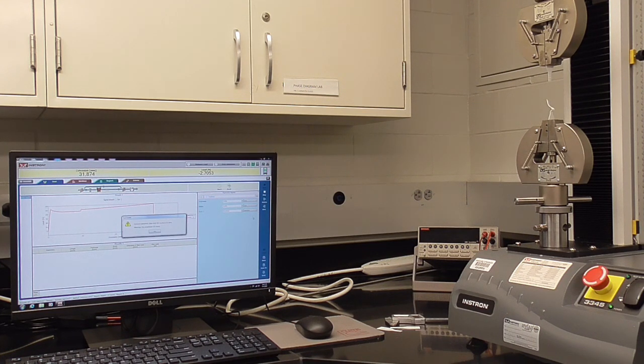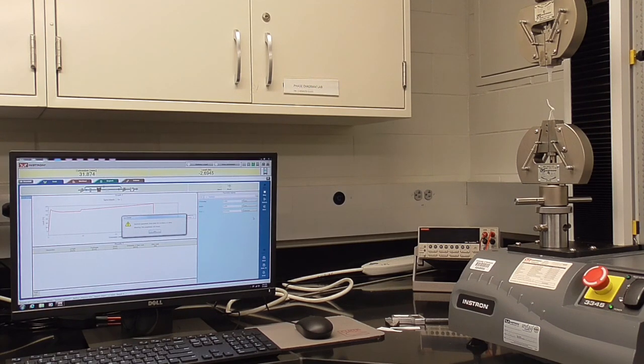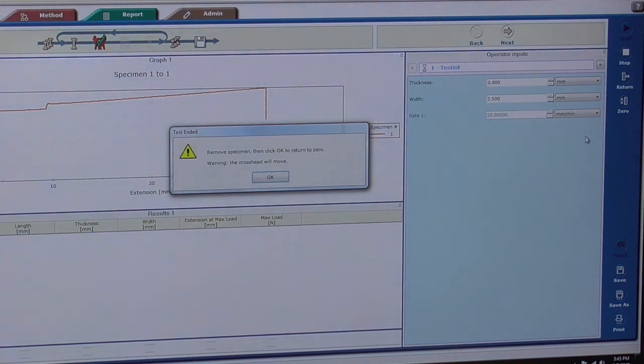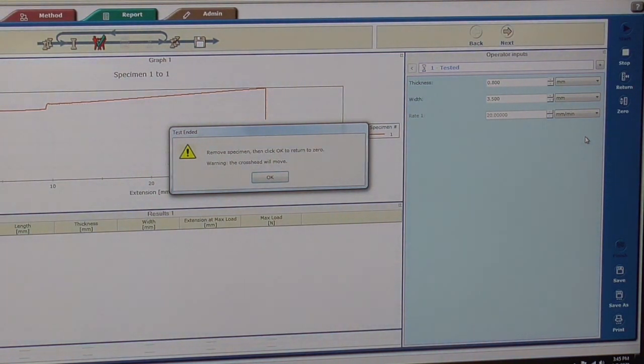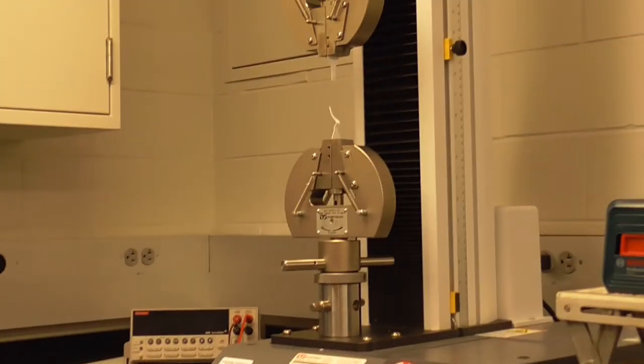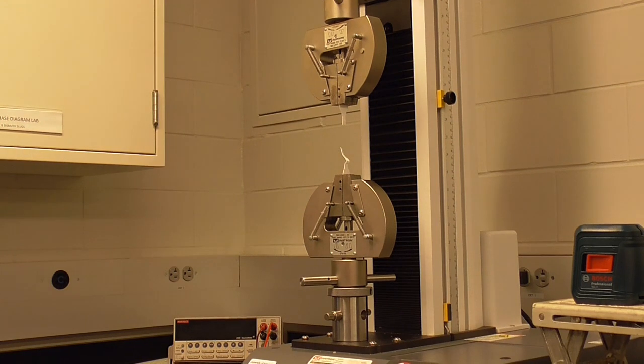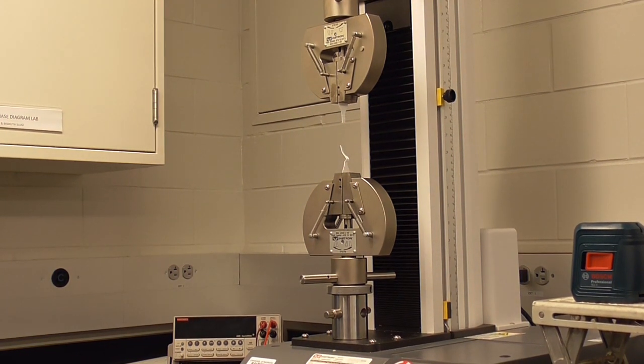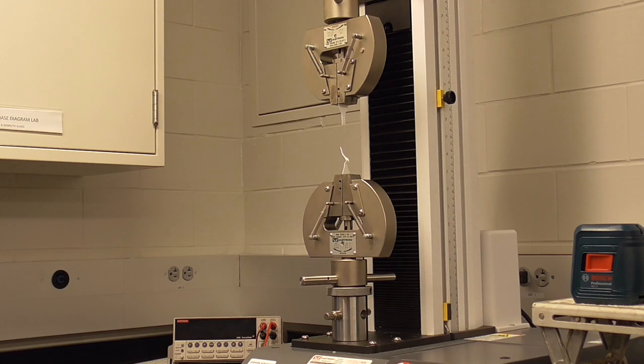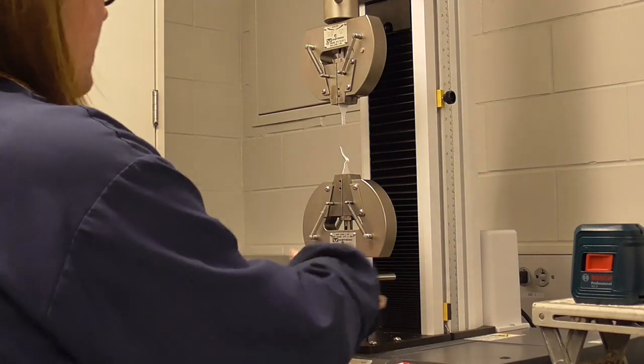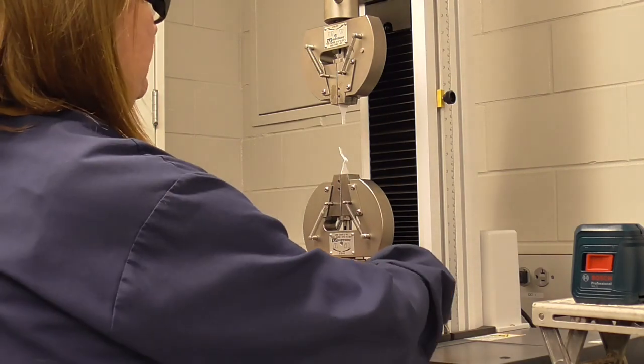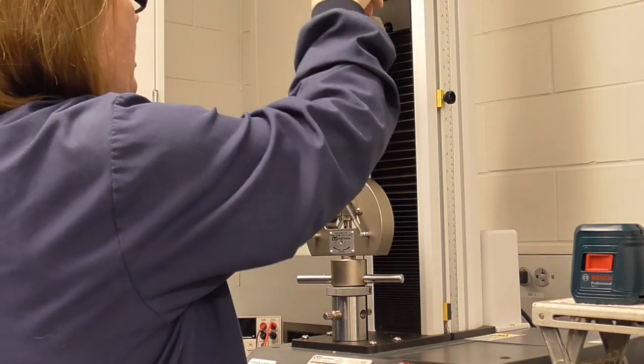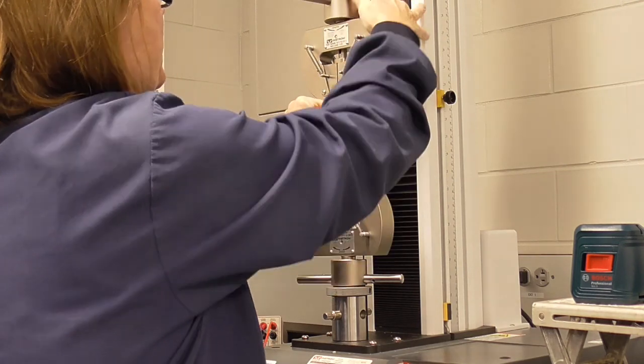That was the sound of the polymer breaking. If I zoom in on the screen, you can see a pop-up here that tells me to remove the specimen and then click OK. We're going to do that. We remove the specimen first in case when we hit OK, the grips are going to move back together to the zero position. If our specimen is a metal, it would crash and damage the load cell, so it's a good habit to take the specimen out at this time. This tells you which way to turn to remove the specimen.